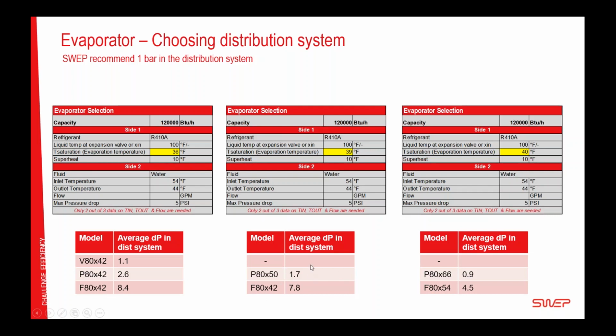And then the same question goes for the average and the high-end evaporator. For this one here, the P80 is probably the Goldilocks choice, and for the really high efficiency, you have to go with the F80, since SWEP's recommendation is more than 1 bar in the distribution system to make sure that it really works during all the conditions. I would say it's the F80 for the highest one. So your choice here, I would go for maybe the P80, my Goldilocks choice, and here I'm forced to go with the F80. So that's the distribution system for you.